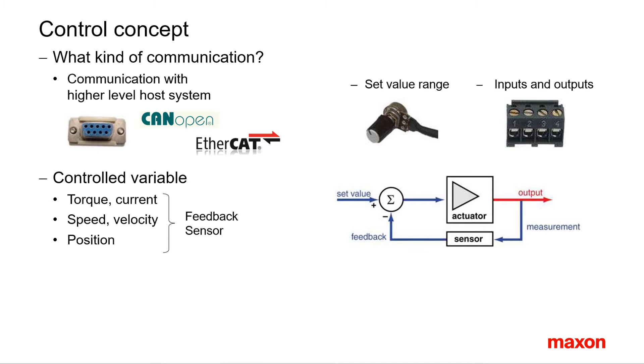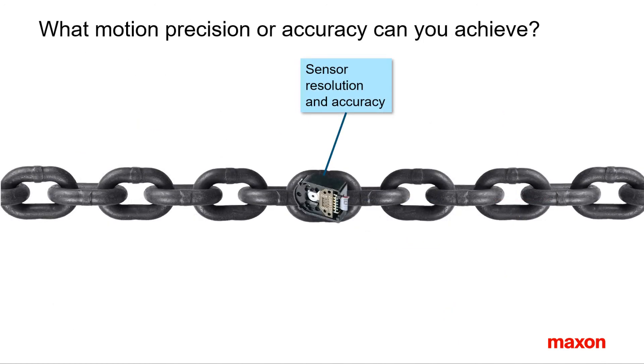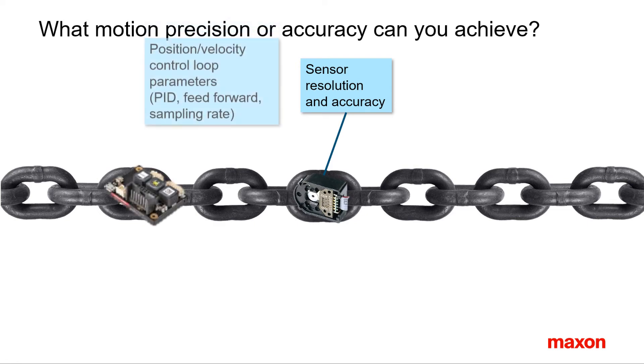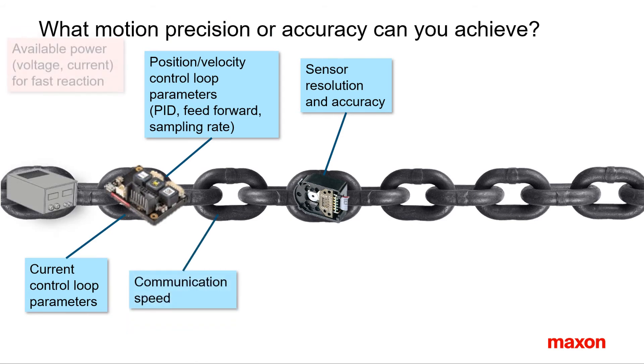Set values could also simply be given as a digital or analog signal. Do we need additional inputs and outputs — for example, for homing or temperature monitoring? Additionally, the range and needed accuracy of the controlled parameter has to be defined. Again, the weakest link in the drive chain and the combination of all factors defines the quality of motion. Typically one might say it's the sensor resolution and accuracy that gives perfect control, but this is just one element. A lot depends on the design of the control loops, on communication between components, and on the available power for a fast reaction.